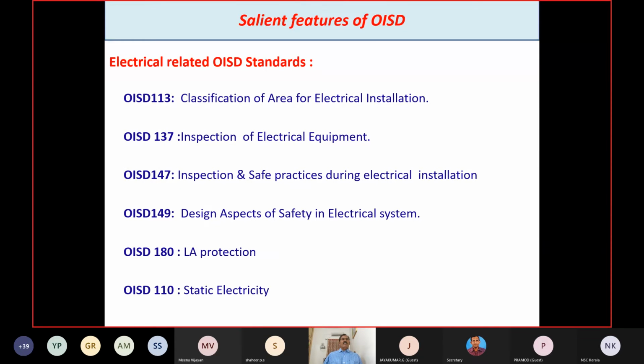And there are so many OISD standards that have been developed, especially for electrical. So the electrical related OISD standards are, now we have discussed 113, the classification of area for electrical installations. The OISD standard 137 is meant for inspection of electrical equipment. The OISD standard 147 is for inspection of safe practices during electrical installations. And OISD standard 149 is meant for design aspects of safety in electrical system. And OISD standard 180 is specially made for lightning arrestor protection. And OISD 110 is made for static electricity.